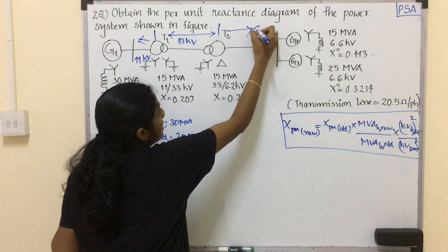For G3: MVA base new is 30 and MVA base old is 25. KV base old is 6.6 kV and KV base new is 6.2 kV. X per unit old is equal to 0.3214. So substituting: 0.3214 multiplied by 30 divided by 25 multiplied by 6.6 divided by 6.2 squared — the value will be 0.437 per unit. Now G1, T1, T2, G2, G3 — all values have been calculated.